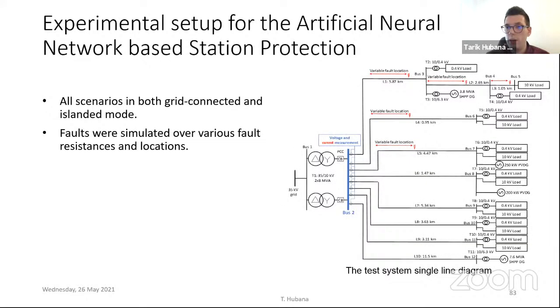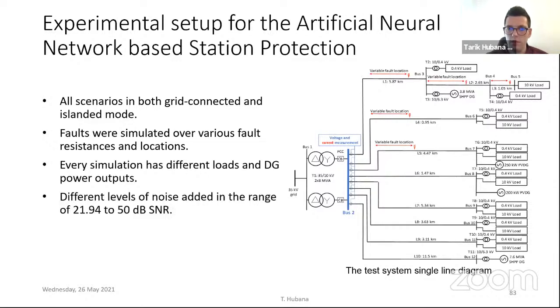Station protection is usually a term used for the full functionalities of the protection of your substations. So in this research, I tried to incorporate all of the standard station protection features by using these presented methodologies. So again, now we measure both voltages and currents, which is common in all secondary and primary substations. The faults were simulated over various fault resistances and locations, now with 3 feeders and different locations. Each simulation has different loads and DG power outputs that are actually set according to the daily load curve in this part of the system.